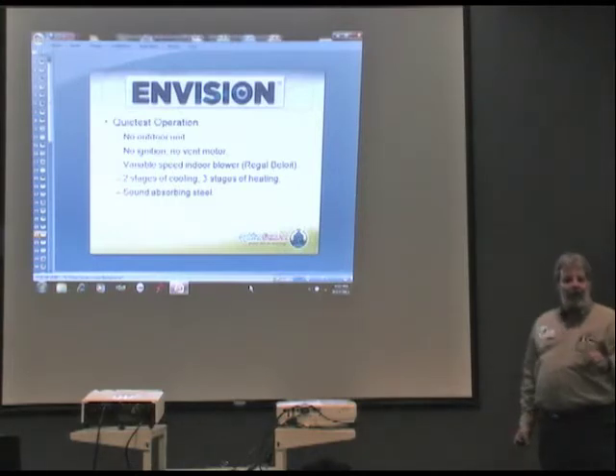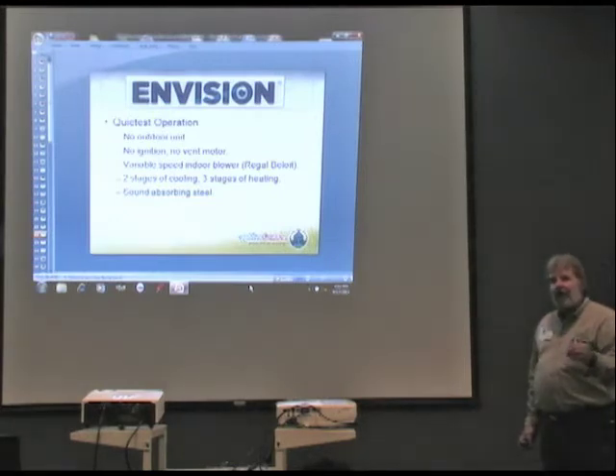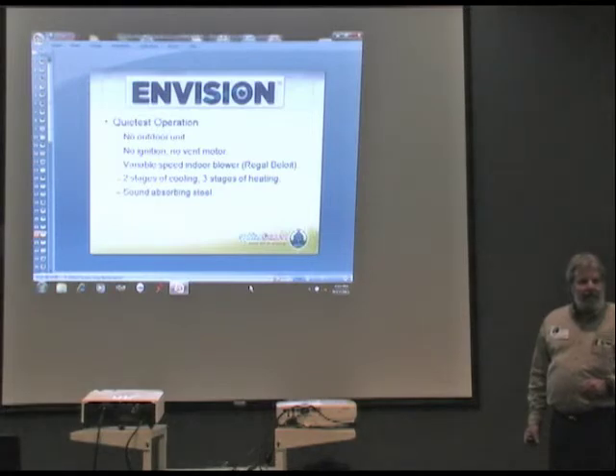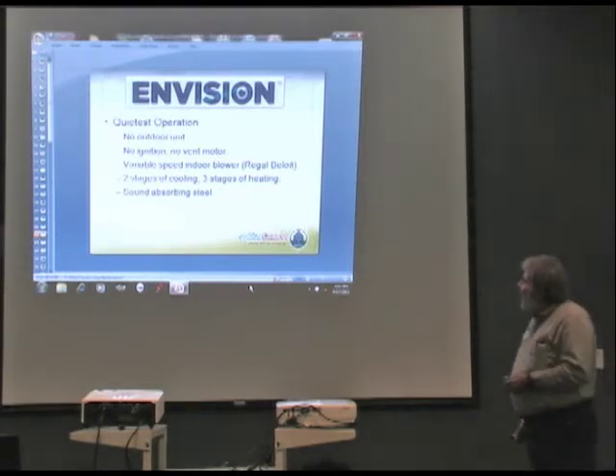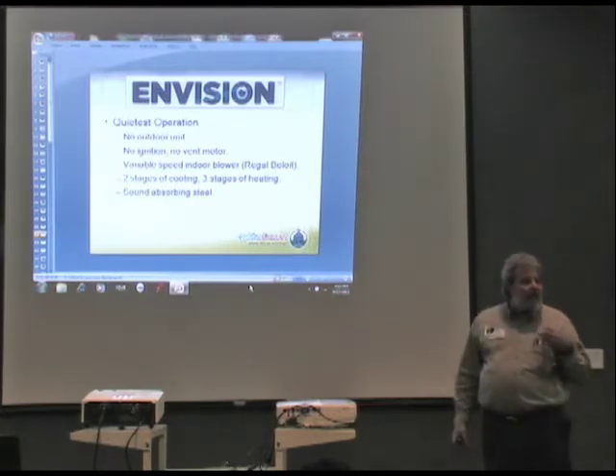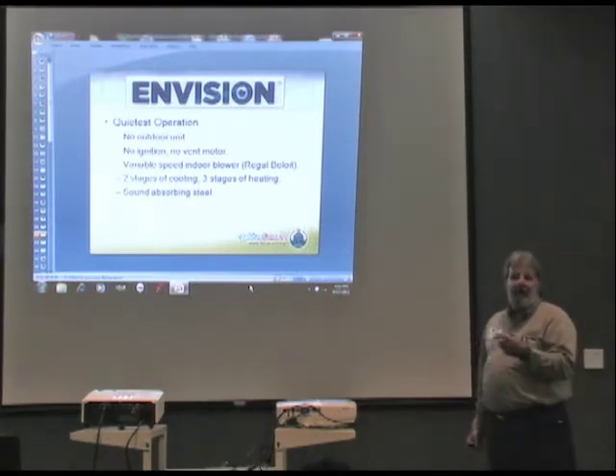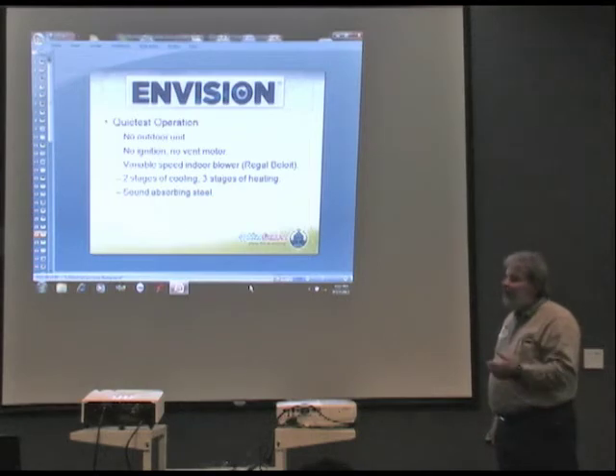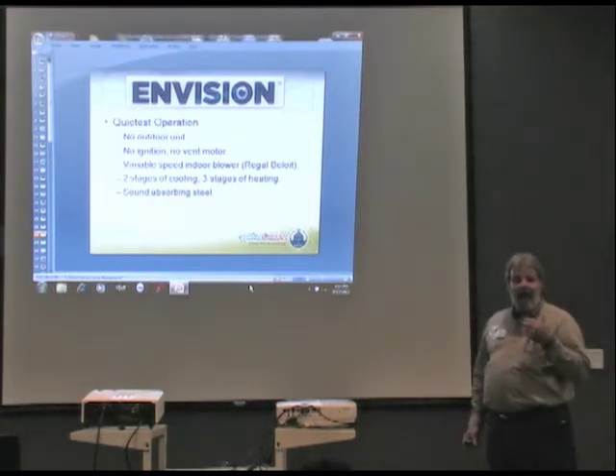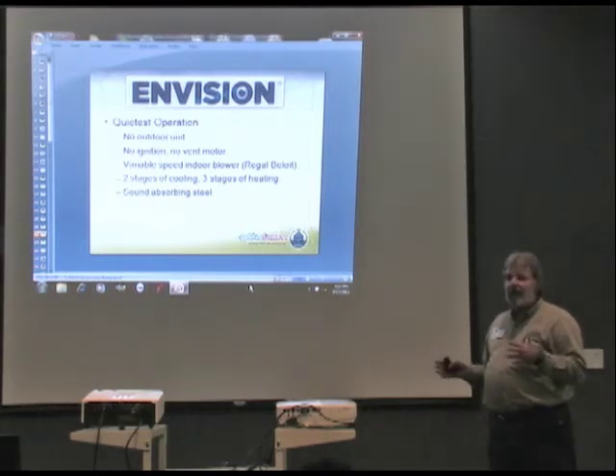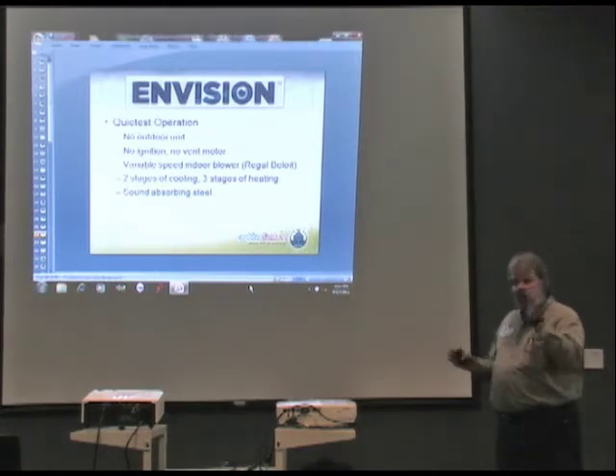I put the backup electric heat in. People say, 'well, you don't need it,' and I know you don't, but there are a couple of reasons. A part might break in the winter, so I can flip you to emergency heat. Or, since we're taking so much heat out of the earth, if we get an extremely cold winter like the last couple of years, the flow center taking that heat out may, every once in a while depending on how the system is set up, shut off.